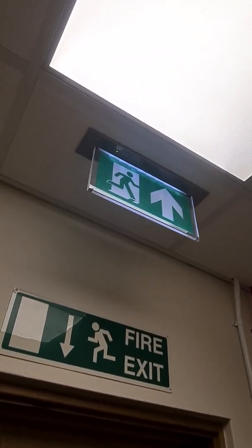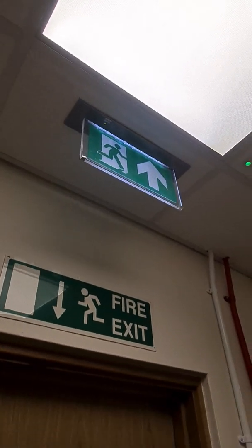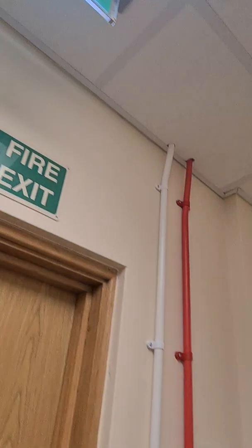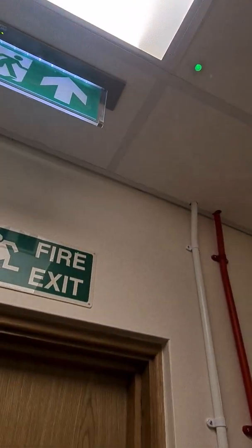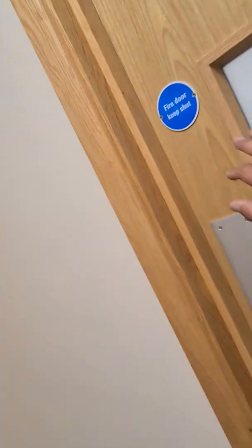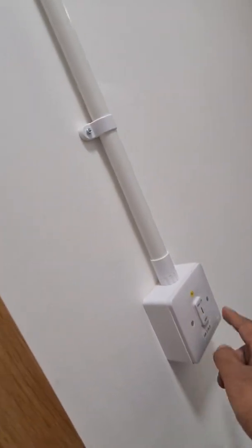And you'll notice as well, not only does this 600 by 600 emergency tile, but it'll also do this exit light as well. Okay, so do you remember I was talking to you about the green LED? Well, that's how your emergency lights should be in their normal position. When you test them, the LED disappears. The other emergency light test point is just located here, and that affects the gents toilet.